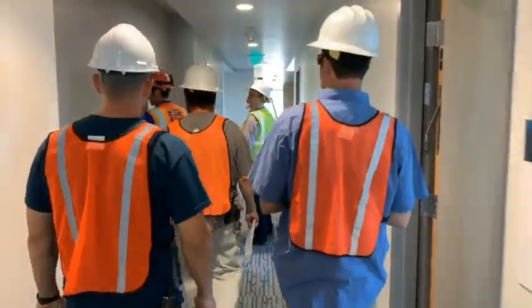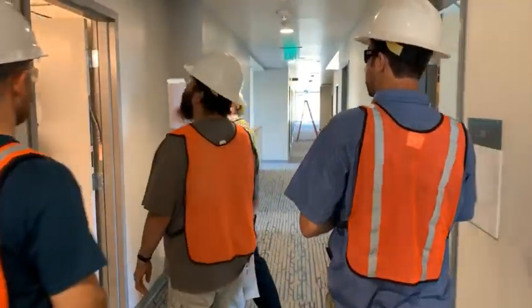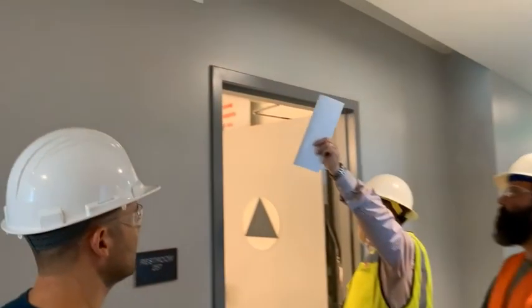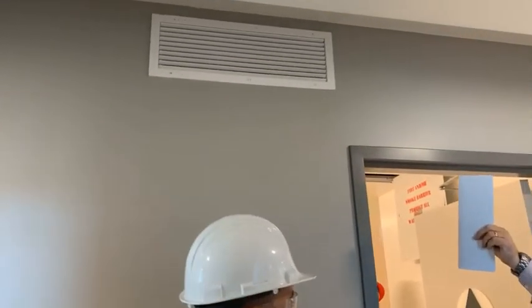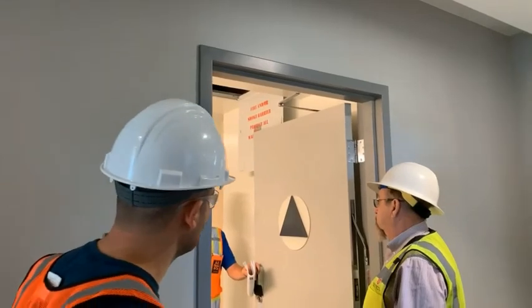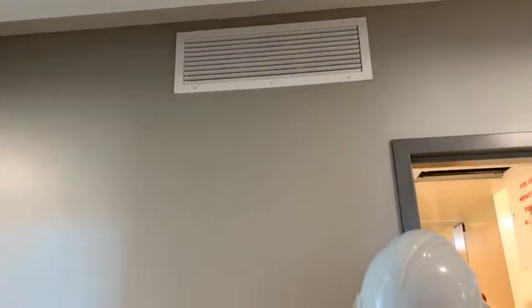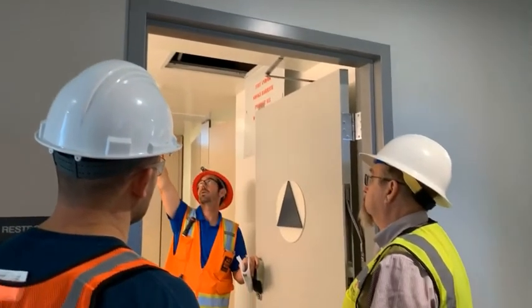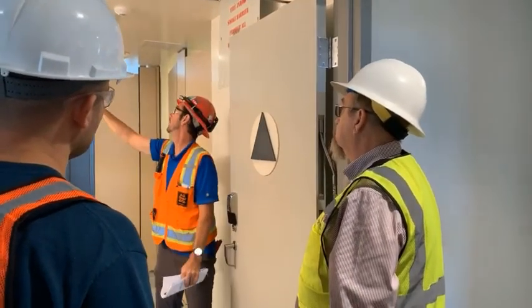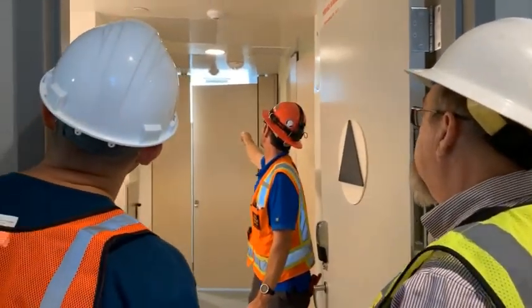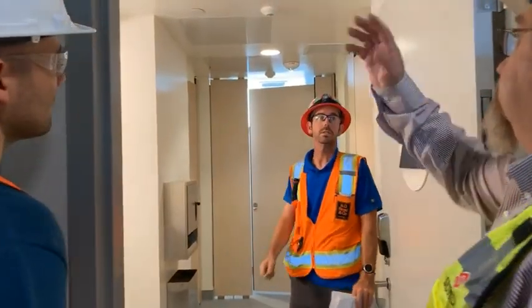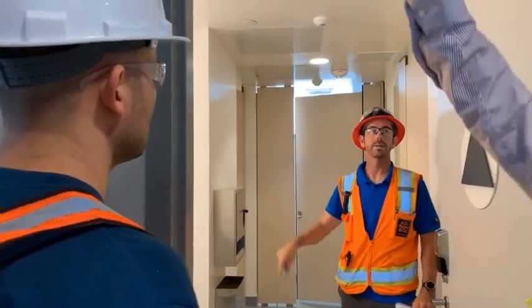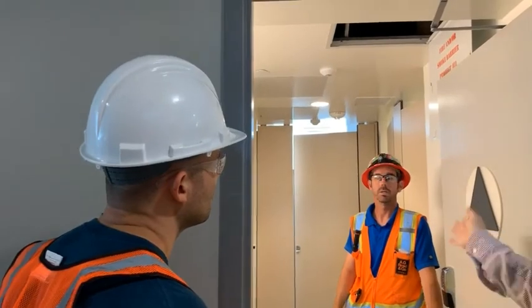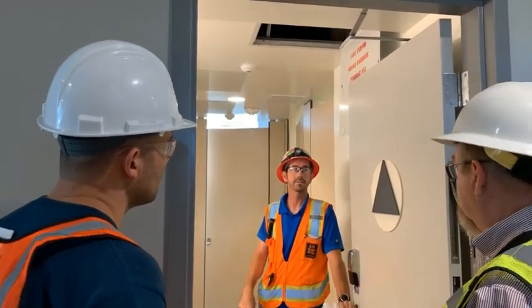So here's our next restroom. What are these vents on the outside for? Those are transfer air. All the makeup air comes from each room unit and the corridor fan coils, and then that's transferring the exhaust air from the corridor into the space. There are about 4 exhaust coils that take it out. So that's bringing the air in from the hallway. If you block that off, you don't get any air and you're going to create a big negative in here. It's not going to be good. Okay.